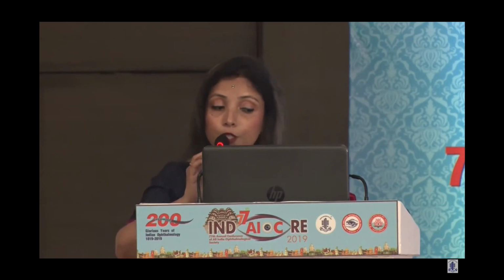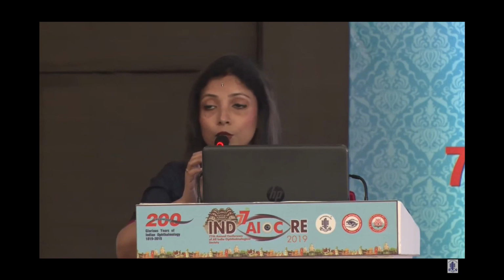The flooring should be seamless, it should be non-porous and smooth, and most importantly, it should be easily and repeatedly cleanable. The walls should have an antibacterial and antifungal paint, dust-proof and moisture-proof. The door should have a self-closing device, and it is always a good idea to have a separate power supply for the costly machines like microscopes and phaco machines.